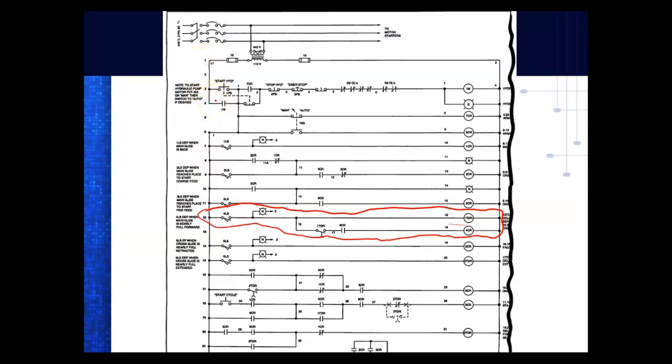And we're not numbering the rungs, we're numbering what we call the lines. So a rung consists of one or more lines. Anything that runs horizontal like this is considered a line. So this rung has two lines. So in motor controls, in our relay logic, we don't number rungs, we number lines.